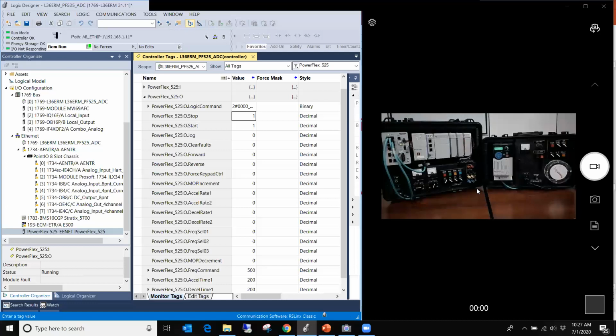So the key components of automatic device configuration, of course, are a logic controller running version 20 or greater, a PowerFlex 750 or 520 series drive, and to take full advantage of the ease of it, we really want a managed switch in this scheme. By doing that, you see we can actually be up and running after a drive is faulted. It took less than 27 seconds that time to completely do it.